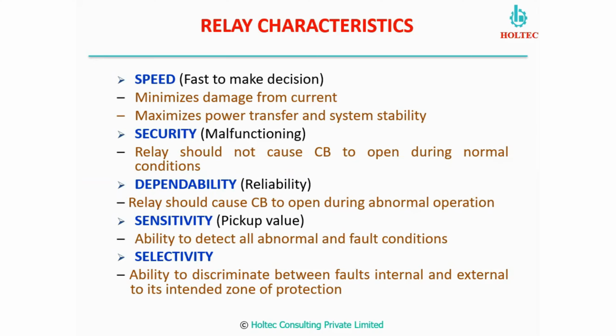Sensitivity depends on the amount of power which is flowing in a system. Suppose in a system a negligible amount of power is flowing, so whatever instruments or relay we have produced, there can be a problem of sensitivity. They cannot sense the fault current properly with this minimal loading condition of the system. So we have to design a relay in such a way that whether it is very light loading or overloading, in all possible conditions, my relay should be able to sense the faulty condition and initiate tripping. Then last but very important is the selectivity.